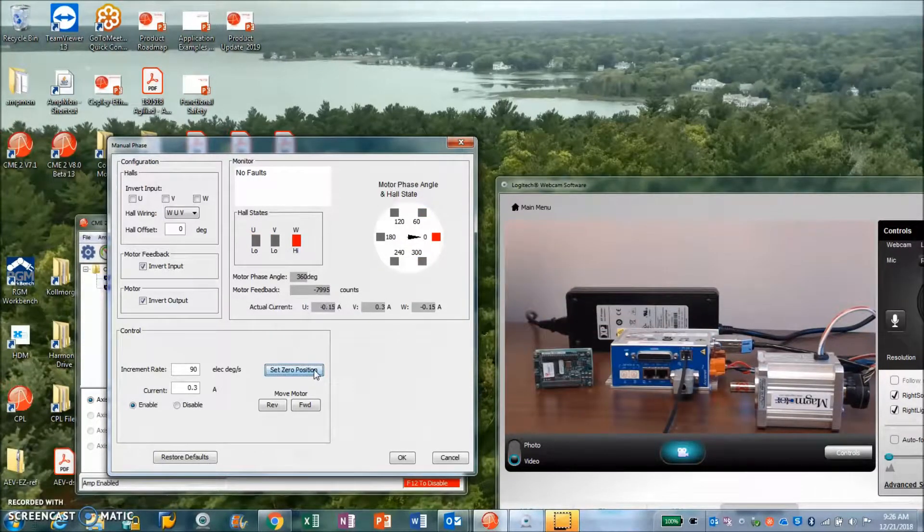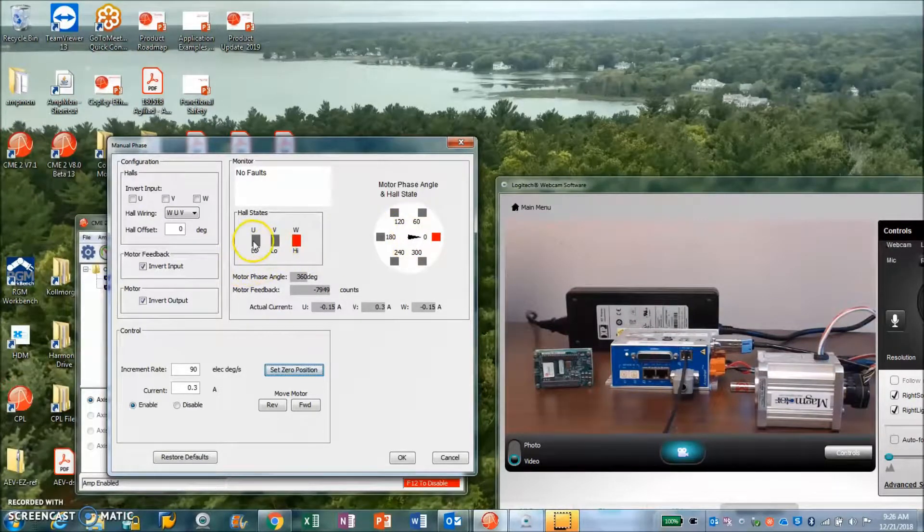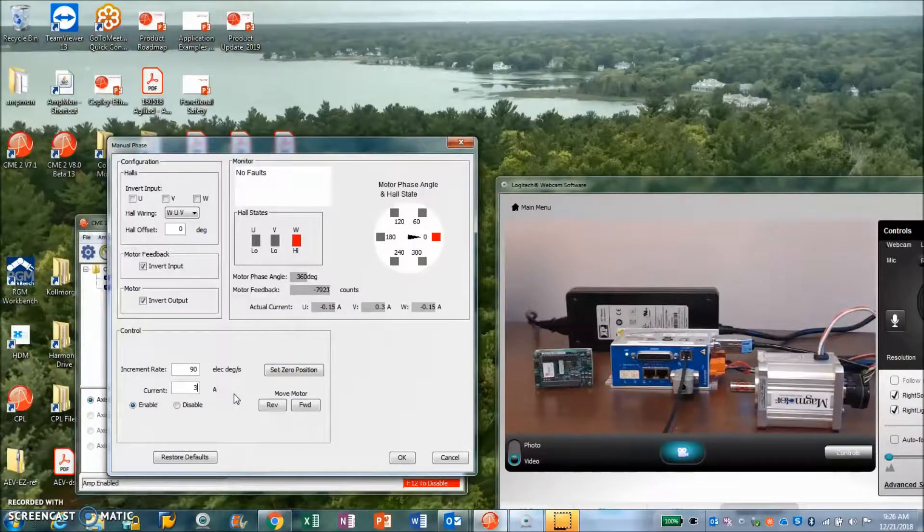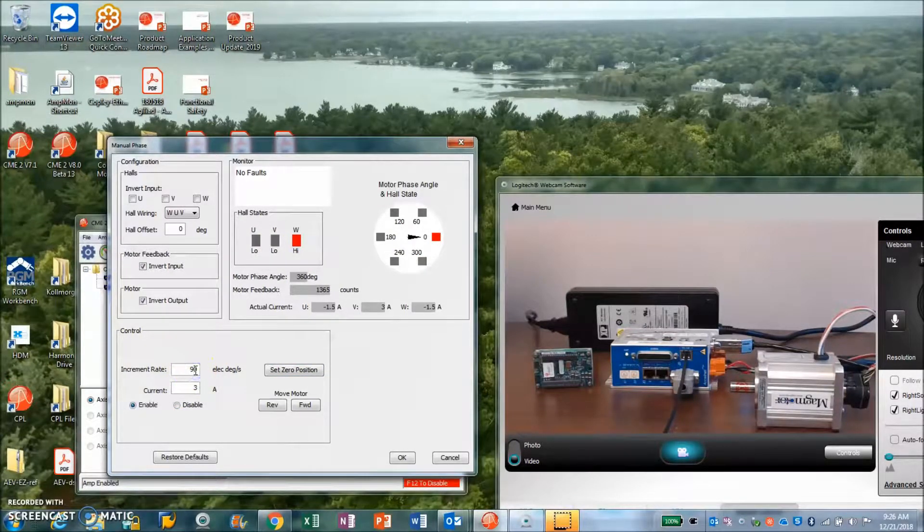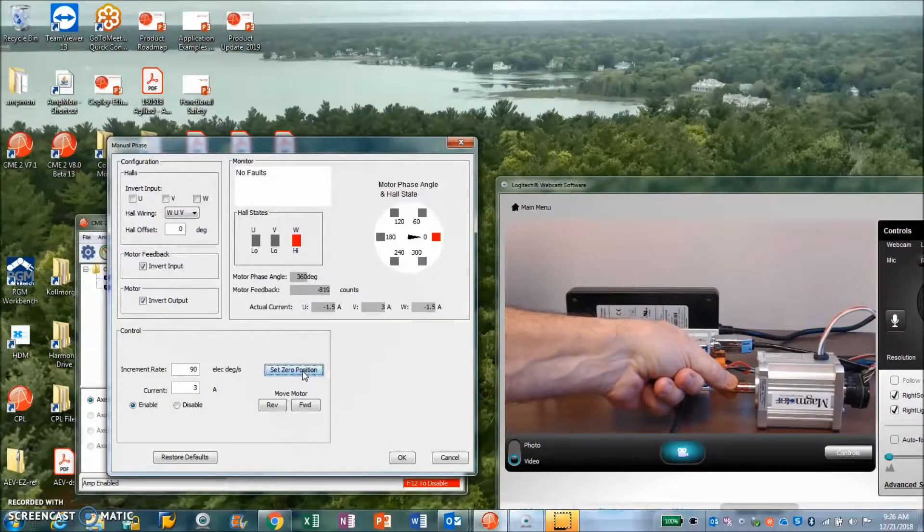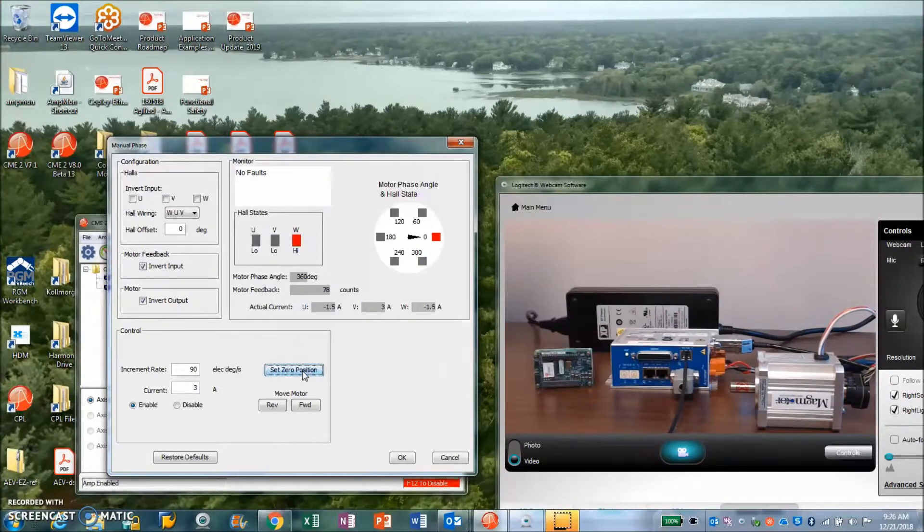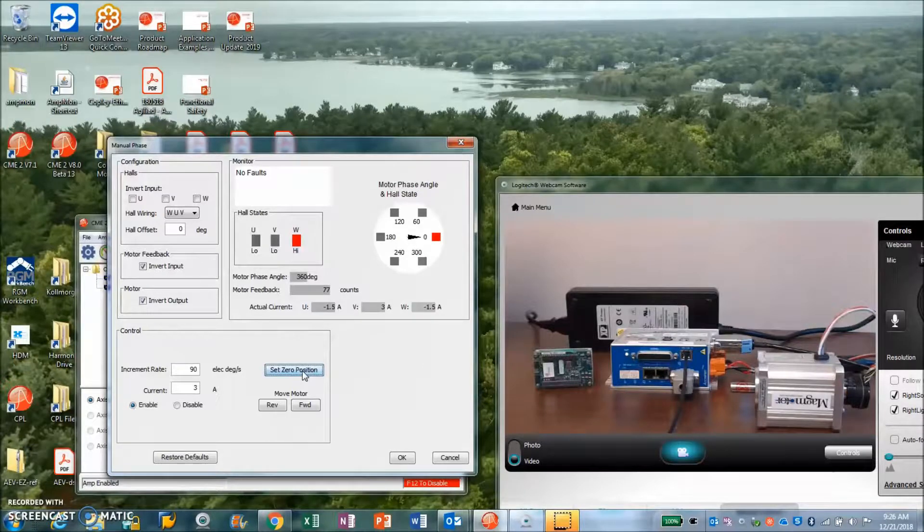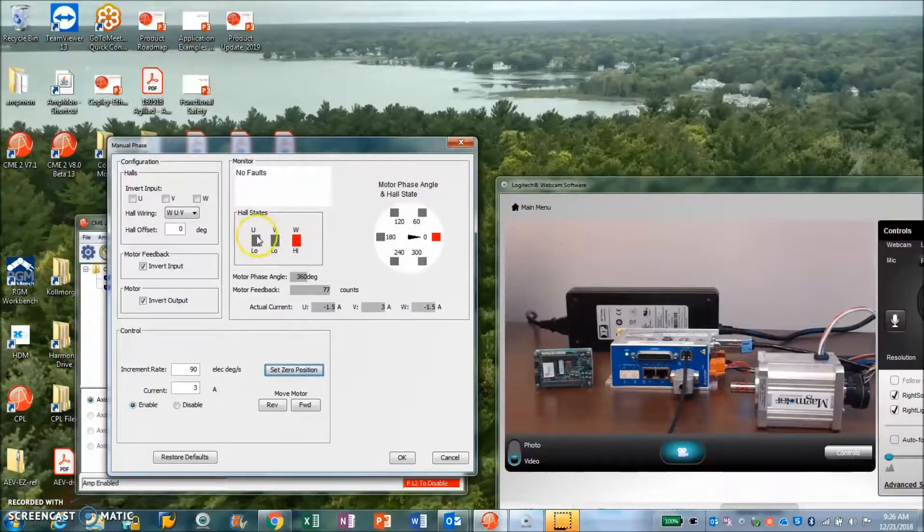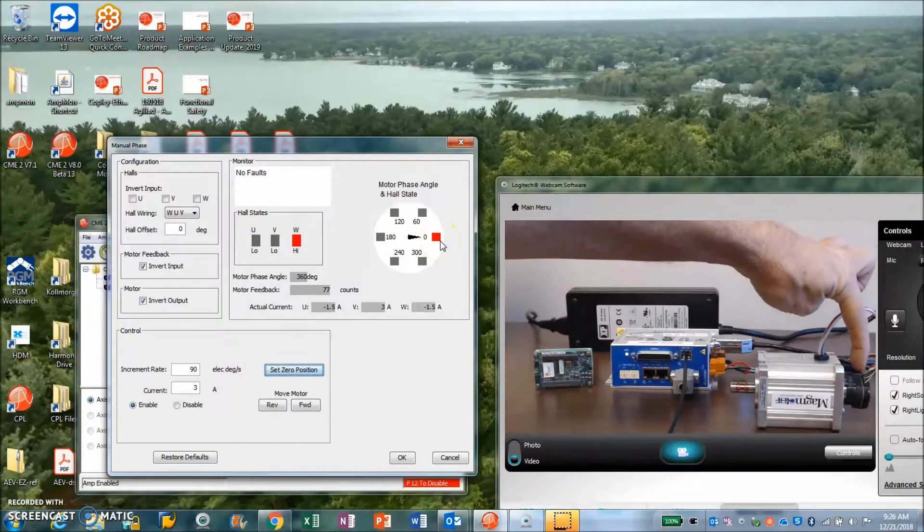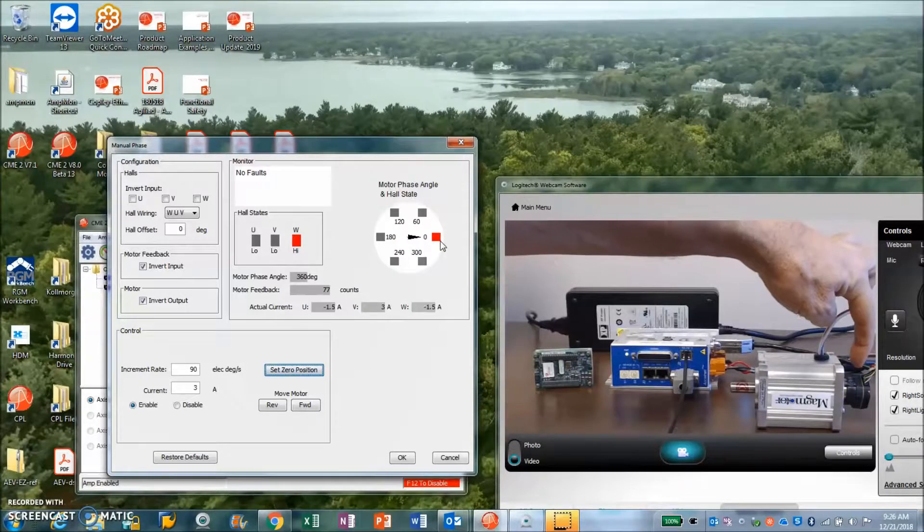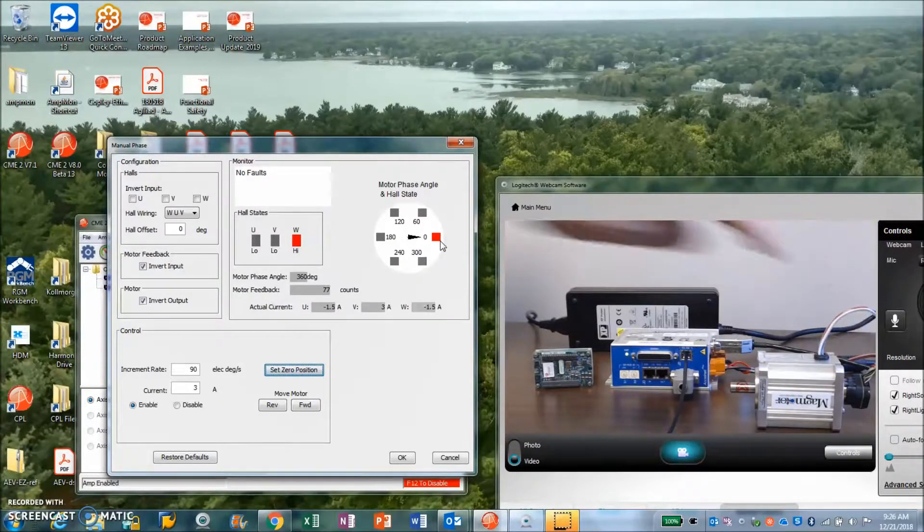I'd like it to hold this Hall state here, UV low W high, so I'm going to give it a boost of current like 10 times, something more along the rated current. Now the motor is more stiffly locked into a position with respect to the electrical cycles, and then I'll mount the encoder on the back and turn it until I see the correct hall code. I'll use the alignment marker first and then tweak it a bit to get to the right hall code.